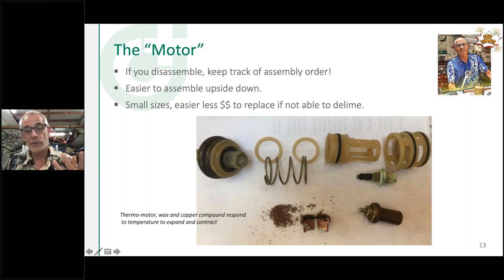For the valve to work properly, it needs good temperature-sensing ability, it needs to be clean, and it needs to move freely inside all the O-rings. Here's an example — one I took apart recently in my shop. Notice this one is already starting to get a little lime scale on the outside of the copper capsule. As that capsule scales up, it can't sense temperature well — water against copper is better than water against a scale layer. As the valve scales up, not only the heat motor but also the O-rings get restricted, and the valve starts to jump: warm, cold, hot, warm. You've got to take it apart, de-lime it, replace the guts, or sometimes just replace the valve.